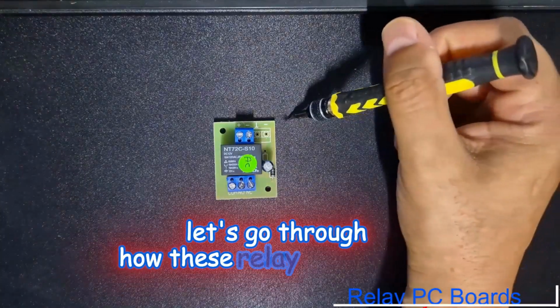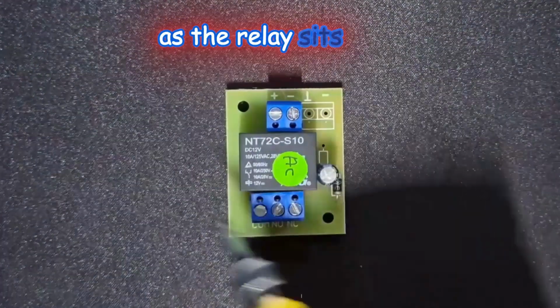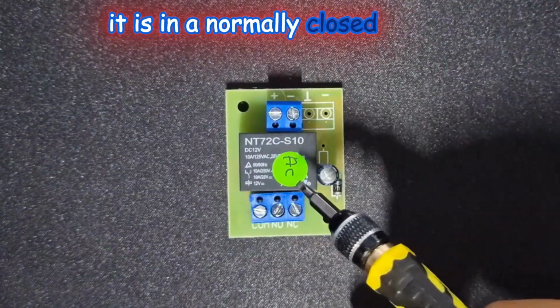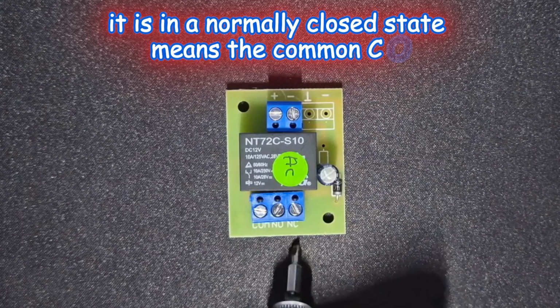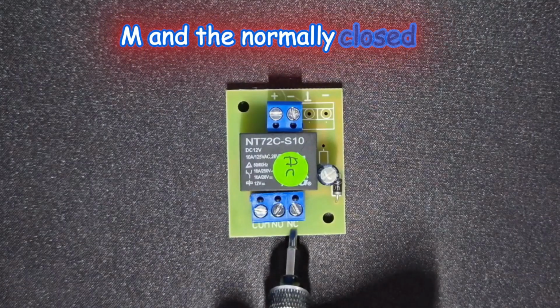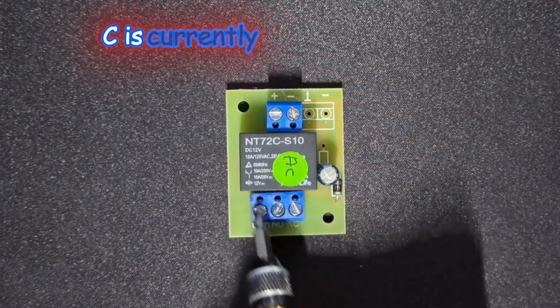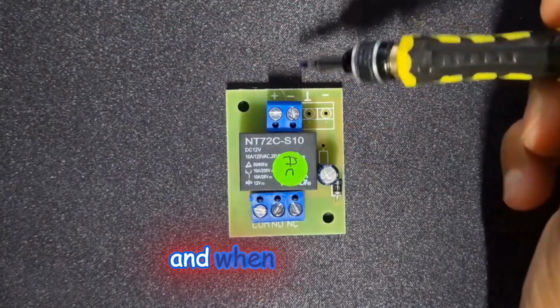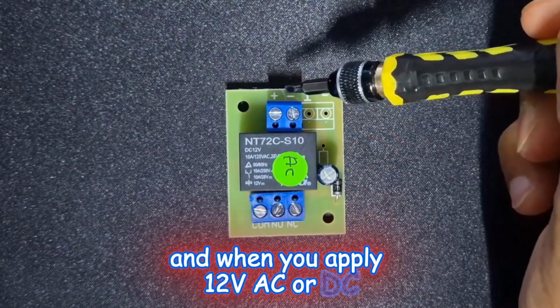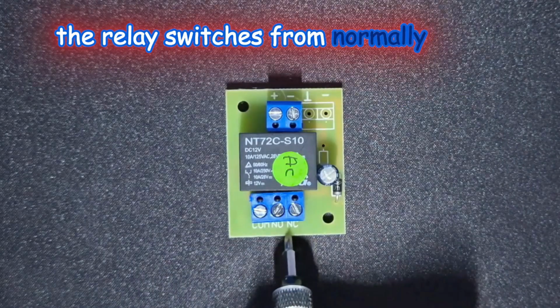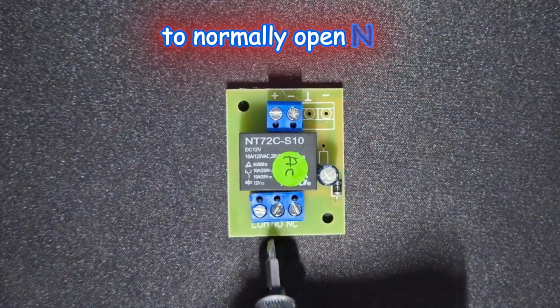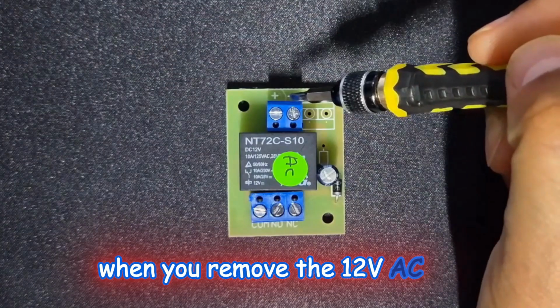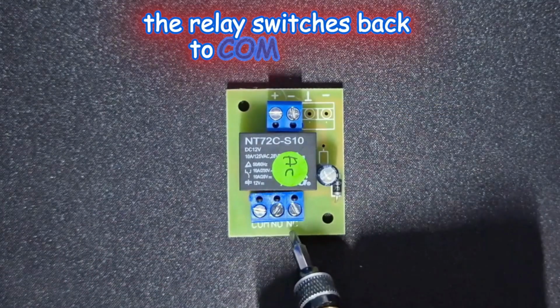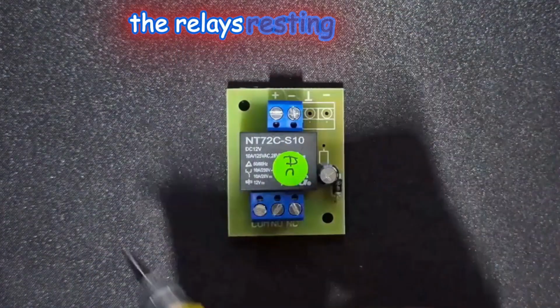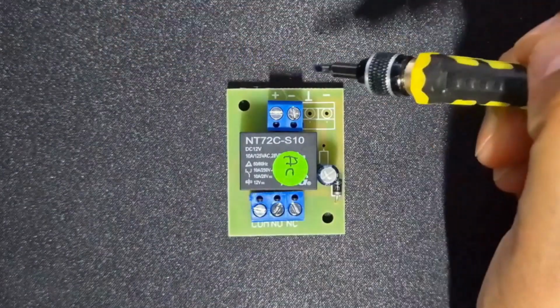Let's go through how these relay boards work. As the relay sits here, it is in a normally closed state. It means the common COM and the normally closed NC is currently in a closed circuit, and when you apply 12 volts AC or DC, the relay switches from normally closed to normally open NO. When you remove the 12 volt AC DC, the relay switches back to common and normally closed. So the relay's resting state is normally closed, and when you apply power, it switches to normally open.